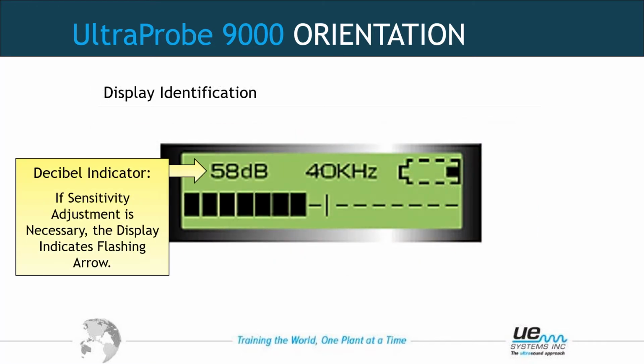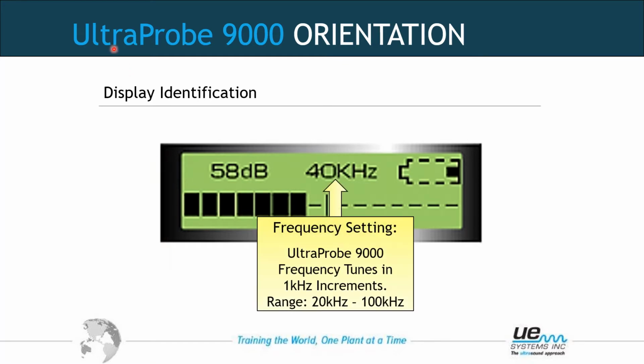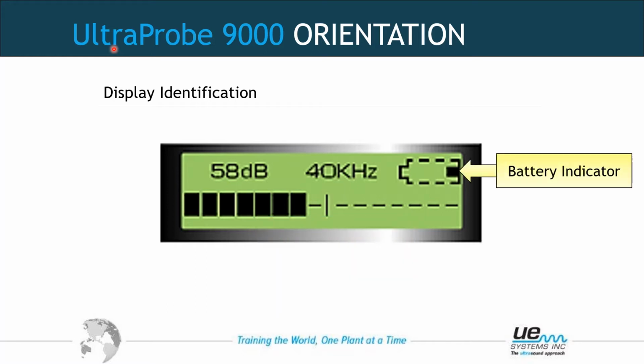The display itself. The decibel indicator. Here it says 58 dB, 58 decibels. The sensitivity is adjusted fairly well as far as this picture goes. If it needed adjusting, arrows would flash to the right or to the left where 58 dB is sitting and no decibel would be present. The frequency setting. The frequency of the Ultraprobe 9000 ranges from 20 kilohertz to 100 kilohertz in increments of 1 kilohertz. 40 kilohertz is the nominal setting for airborne sounds. The battery indicator. This indicates we have little battery left. Otherwise, all bars would be lit in the battery if it was a full charge.